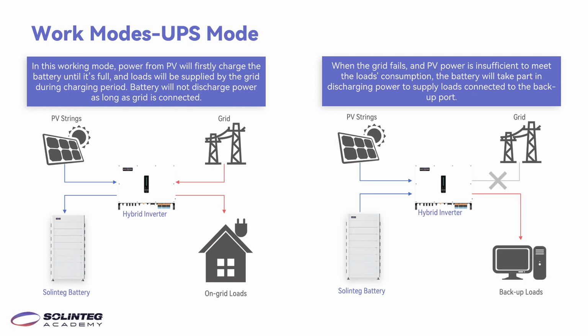This is the UPS mode, which is usually used in some places where the grid is frequently interrupted. So power from PV will first charge the battery until it's full. The load will be supplied by the grid during the charging period. The battery will not discharge power as long as the grid is connected. When the grid fails and PV power is insufficient to meet the load's consumption, the battery will take part in discharging power to supply the loads connected to the backup side.